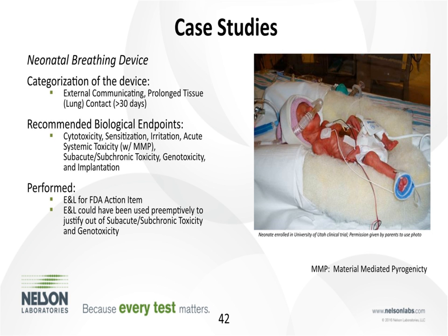For the next case study, we have a neonatal breathing device. This device supplies humidified and heated oxygen to a neonatal patient and is in direct contact with the lungs. The categorization of the device is external communicating, prolonged lung tissue contact of greater than 30 days. The recommended biological endpoints per ISO 10993, you can see there.